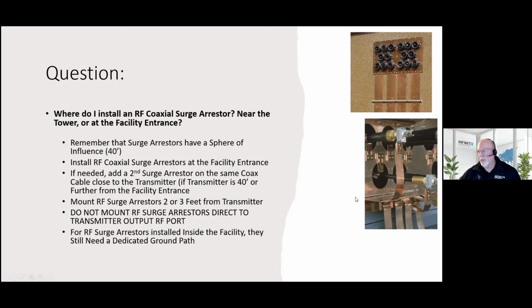So I can have two on the same coax line. That might add impedance. Well, it's going to add a little impedance, but remember induced surge current. So you have one here. It's doing its job. It'll remove surge current there. But if your radio is 200 feet away, it's still susceptible to induced surge current. And I'm going to install that right on the RF port of my radio.